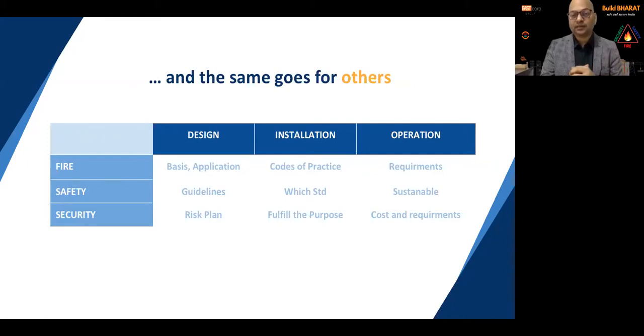So when it comes to the design stage, it is very important that you need to know your design application. You can't have a system where the wrong system has been designed. There are instances where a transformer has been protected with a sprinkler system, when ideally it should be a spray system. People don't know the difference between water spray and water sprinkler systems.